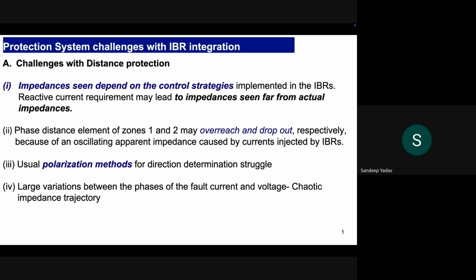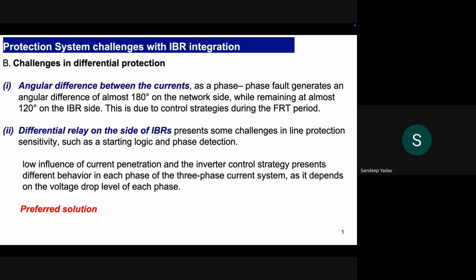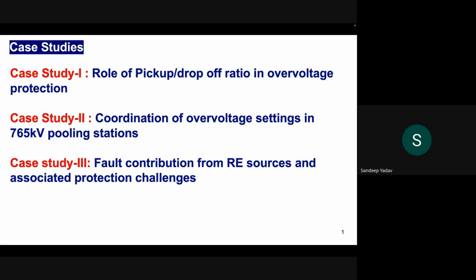So this was the basic theory. We all have been discussing it for the past few years, or over a decade. What I really want to go into is the case studies that we have seen in our system. The first case study talks about the role of pickup to drop-off ratio in case of overvoltage protection. The second one is the coordination of overvoltage settings in different substations.